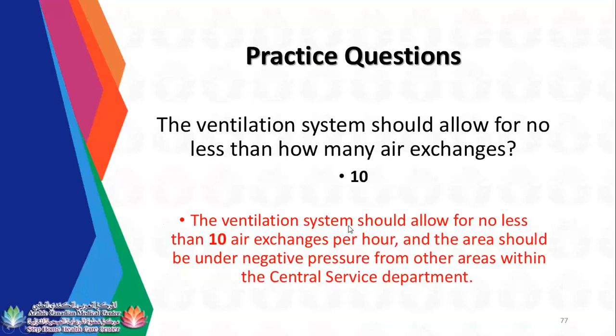Anyway, if there's no area stated, you need to focus that in CSSD there are only 4 air exchanges and 10. The PASS 4 is the only one with 4, the sterile storage, with positive air pressure, and the rest has 10 air exchanges, and the only one with negative air pressure is decontamination. The rest is positive air pressure. Just remember PASS 4, the 4 air exchanges, sterile storage has the only different air exchange value in all areas in CSSD. The rest has 10: decontamination has 10 air exchanges, prep and pack has 10 air exchanges, and your sterilization room has 10 air exchanges.